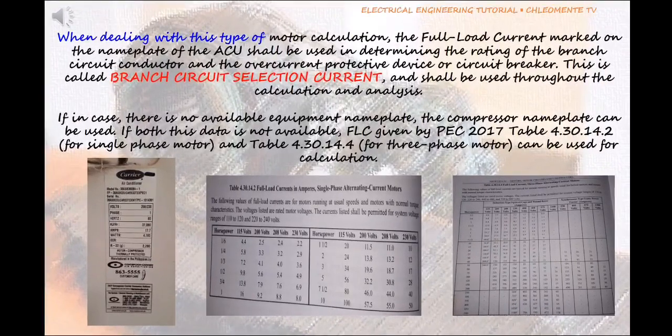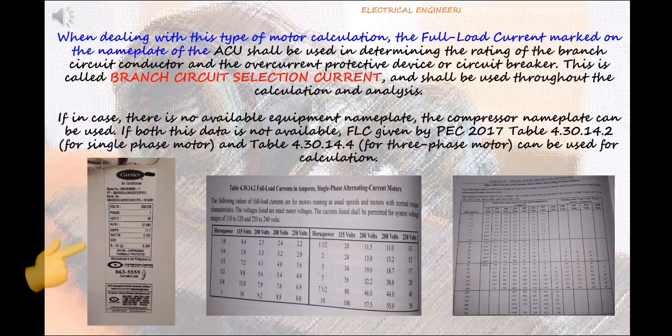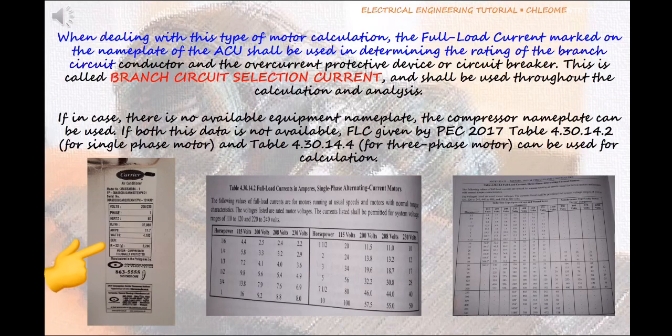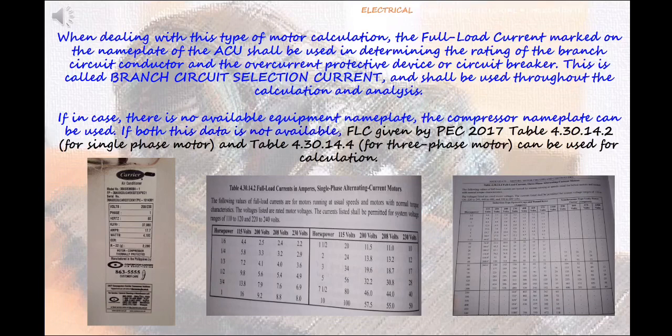When dealing with this type of motor calculation, the full load current marked on the nameplate of the ACU shall be used in determining the rating of the branch circuit conductor and the overcurrent protective device or circuit breaker. This is called branch circuit selection current and shall be used throughout the calculation and analysis. If there is no available equipment nameplate, the compressor nameplate can be used. If both this data is not available, FLC given by PEC 2017 Table 4.30.14.2 for single phase motor and Table 4.30.14.4 for three phase motor can be used for calculation.